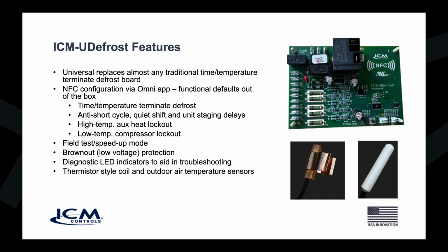So this UDefrost board replaces almost any traditional time or temperature terminate defrost board. It uses your smartphone and the ICM OMNI app, which is free, and the technology of near field communication. This is much like contactless payments like Apple Pay. You bring your device, for example your iPhone or an Apple Watch, near the reader, it makes a little blip, and then it transfers your money. In this case, it's using near field communication just like that, but instead of transferring money, we're transferring a program where you set up all of your functions: your time and temperature set points, defrost terminate, and interval cycles. Then you just program that right into the device.